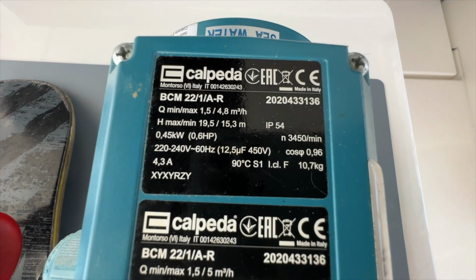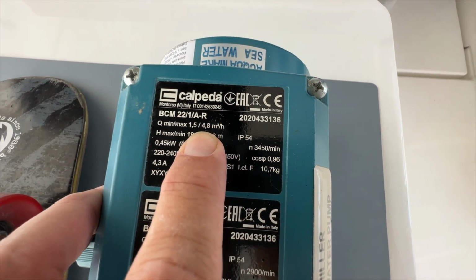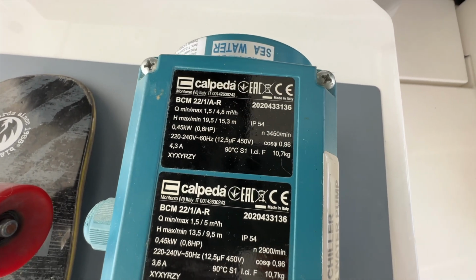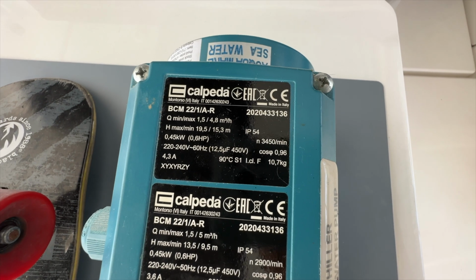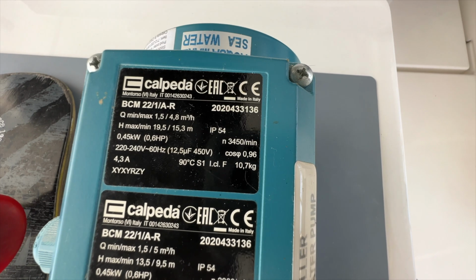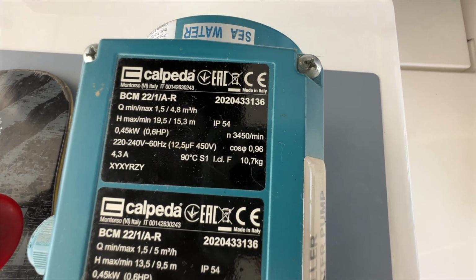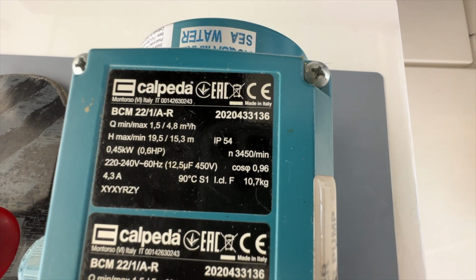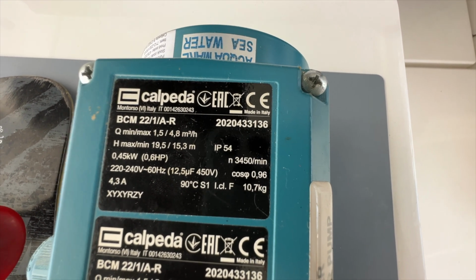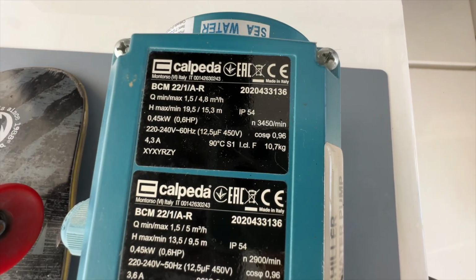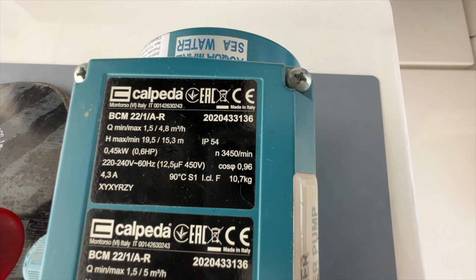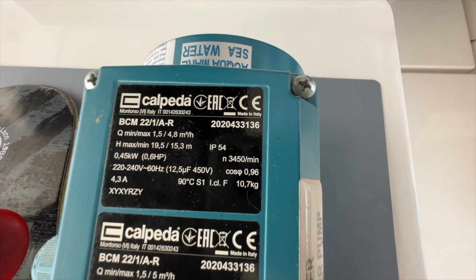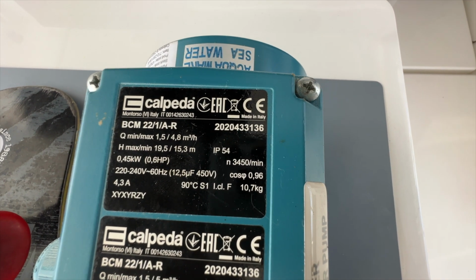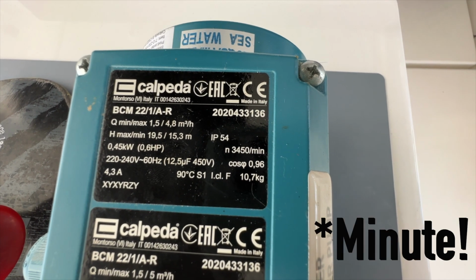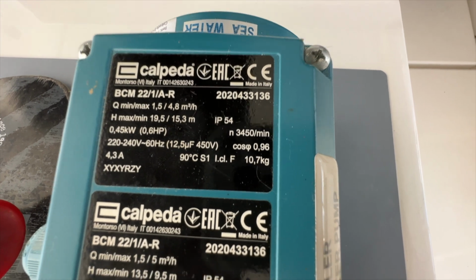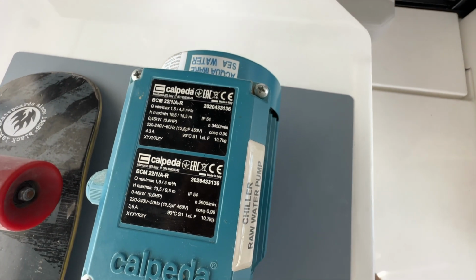The Calpeda says 4.8 cubic meters per hour. Well, why would they make it easy? So we have to convert liters to cubic meters and hours to minutes. There's 1,000 liters in a cubic meter, so that's 4,800 liters per hour. Now we just go from hours to minutes: 4,800 divided by 60. 48 divided by 6 is 8, so 80 liters per minute max. The other one was 76.6, so the sanity check checks out.